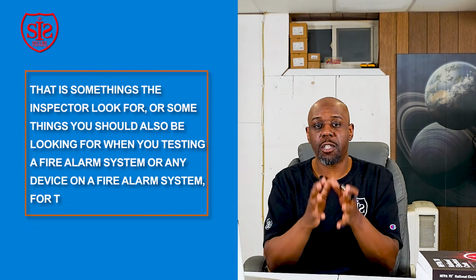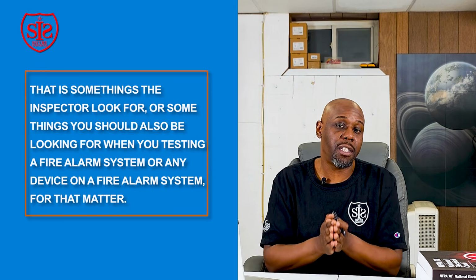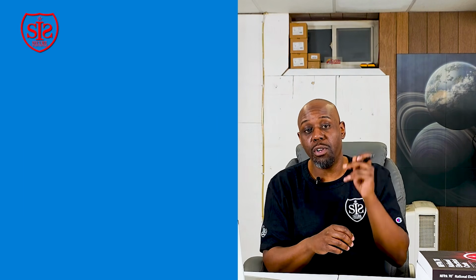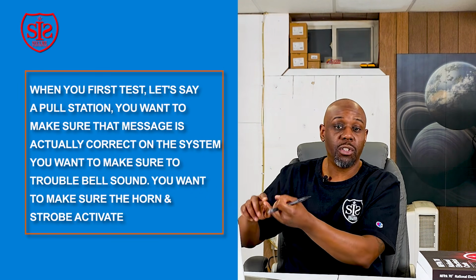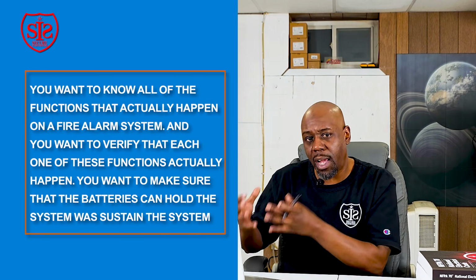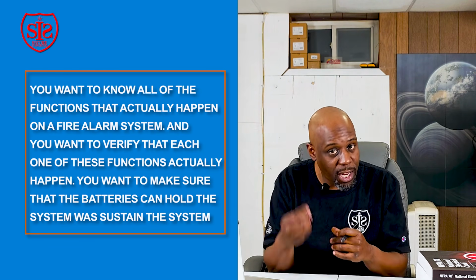Now, there's some things the inspector looks for, or some things you should also be looking for when you're testing a fire alarm system or any device on a fire alarm system for that matter. When you first test, let's say, a pull station, you want to make sure that the message is actually correct on the system. You want to make sure the trouble bells sound. You want to make sure the horns and strobes activate. You want to know all of the functions that actually happen on a fire alarm system, and you want to verify that each one of these functions actually happens.